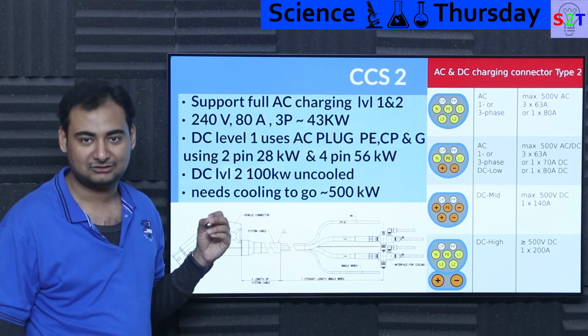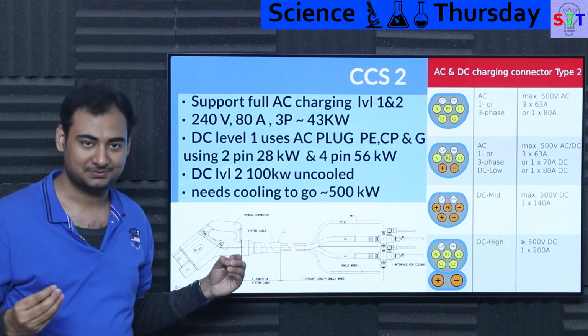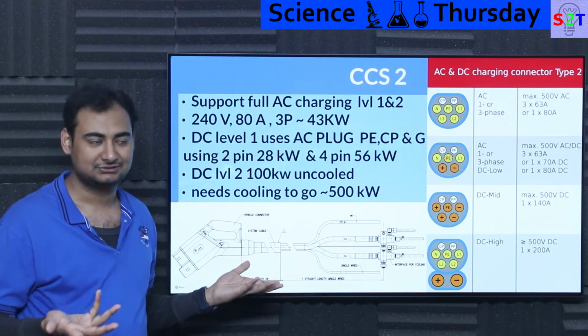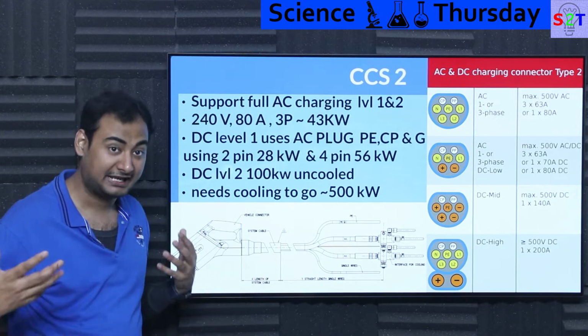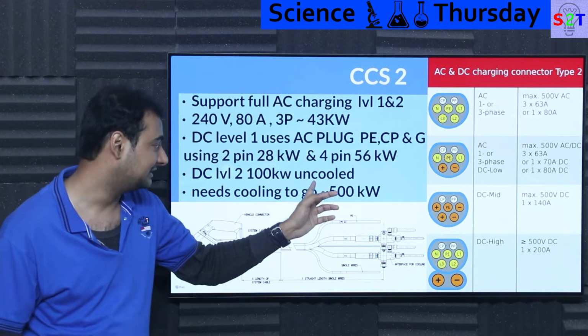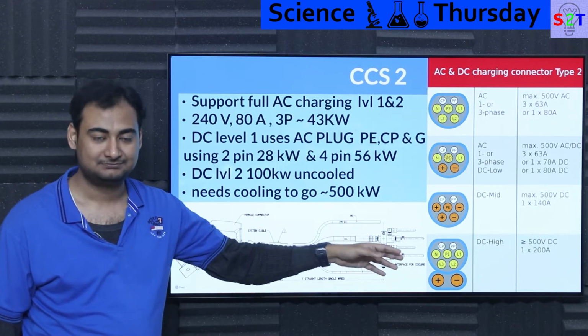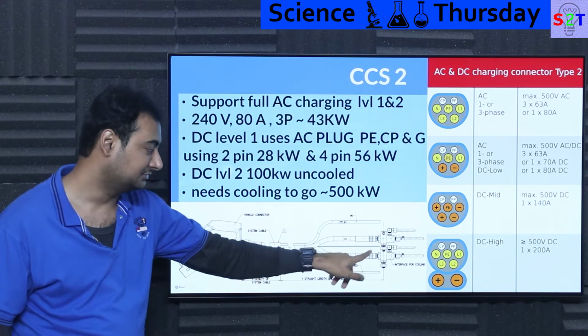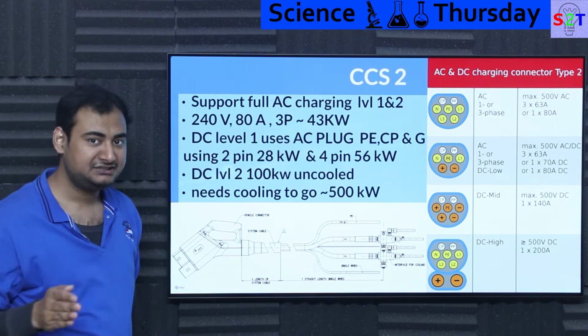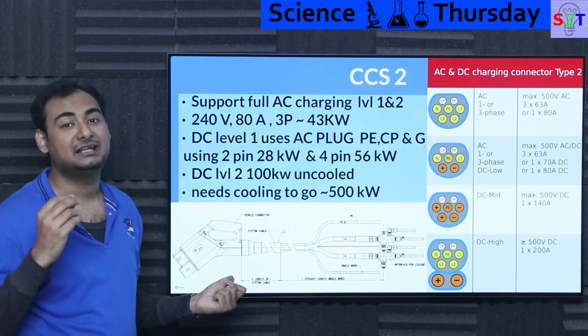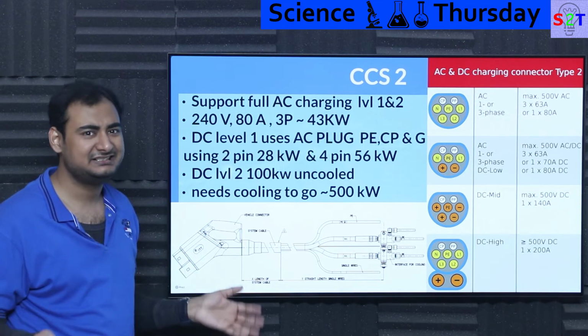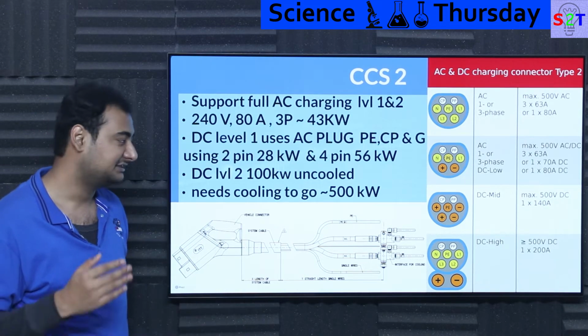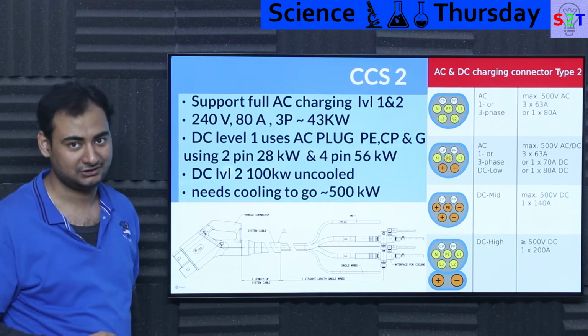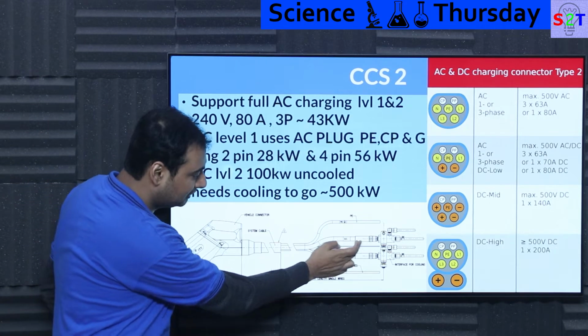So the cable had a copper limitation, meaning it cannot use very thick copper bus. So they are like, okay, we can reduce the copper. Then how the heck do you carry hundreds of amps? This puppy can go around 200 amps. How the heck do you do that? You add cooling to this. If you are going with any charging standard that is using CCS2 and has very high capacity, even any DC fast charging, that is DC level 2 charging above 100 kilowatt, generally they will have liquid cooling in it. The pipe will basically have a coolant channel for it.